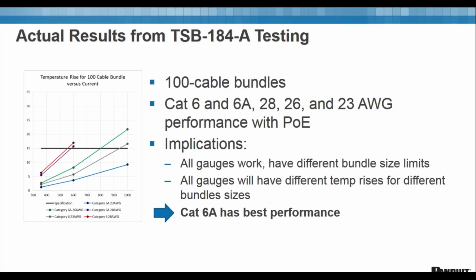You can see here there's a few observations you can draw from it. First of all, on the 28 gauge side, and this is for a 100 cable bundle, it does get hot, but 28 gauge absolutely can support PoE. There's no issues with running these higher power levels over a 28 gauge system. You just have to be more aware of the bundle size.